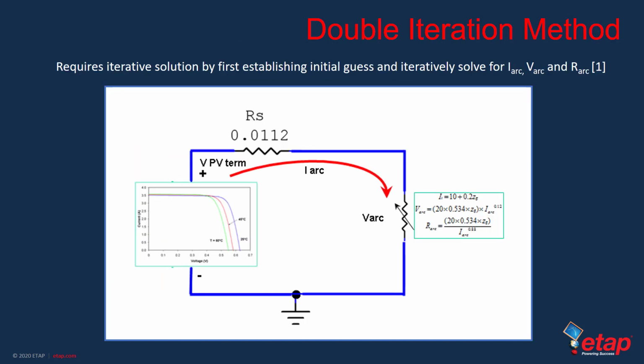In the previous slide, we saw a high-level representation of the equivalent DC power circuit for a voltage-behind-impedance type of source. However, since we're discussing photovoltaic systems, and as I explained during the 2015 electrical safety workshop, the photovoltaic system short circuit characteristics are nonlinear, and for a high portion of the operating region behave almost as constant current sources. The operating voltage of the photovoltaic system is also influenced by a controller, which is typically not shown in most diagrams, in particular in high-level equivalent systems. The maximum power point tracker or controller biases the operating voltage towards the maximum power delivery point.